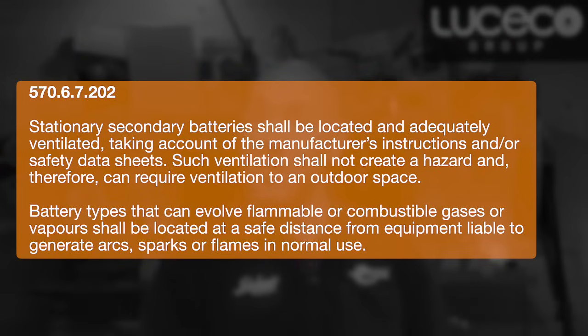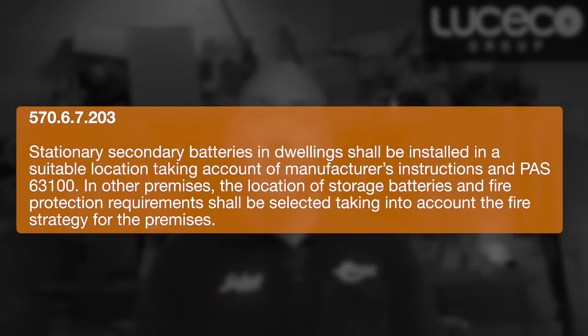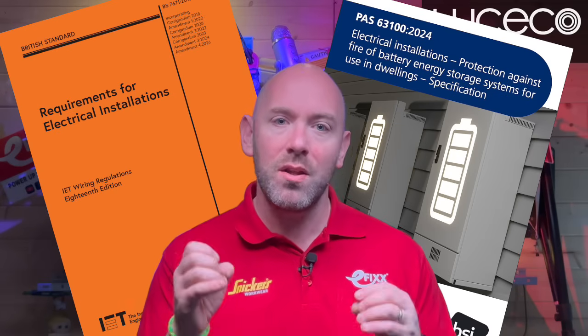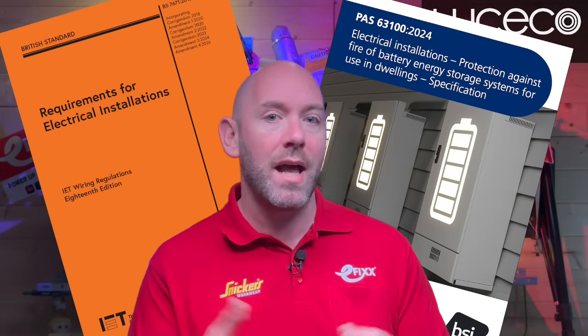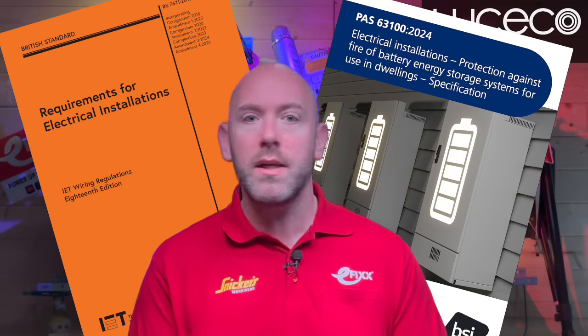Regulation 570.6.7.202 requires batteries capable of producing flammable gases to be installed away from ignition sources. And for dwellings, Regulation 570.6.7.203 points you directly to PAS 63100. So BS 7671 is setting the requirement, but PAS 63100 is giving you the detail on how to apply it in domestic installations. Isolation is also critical.